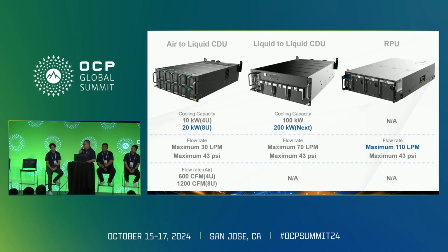For the air to liquid CDU, now we have 20 kilowatt solutions. For the liquid to liquid CDU, the highest cooling capacity we can reach right now is 100 kilowatts. Meanwhile, our CDU department is also working on the next generation CDU, which can support up to 200 kilowatts cooling capacity in the future.